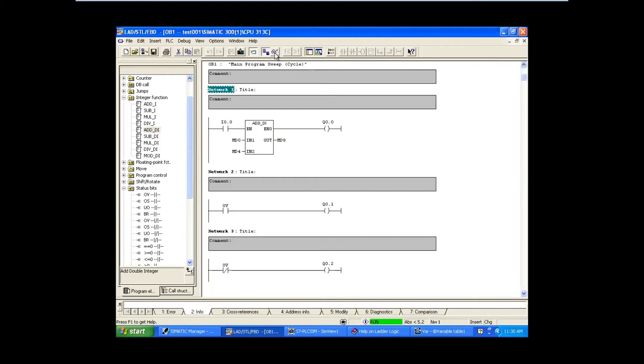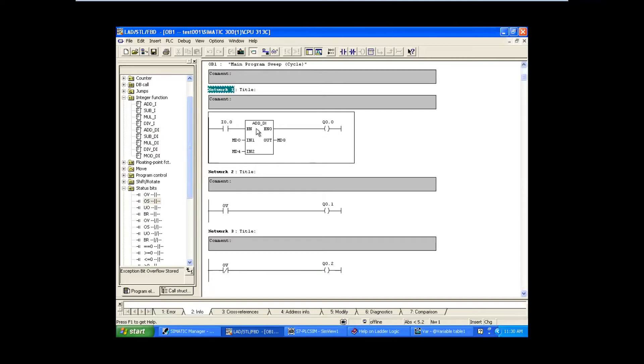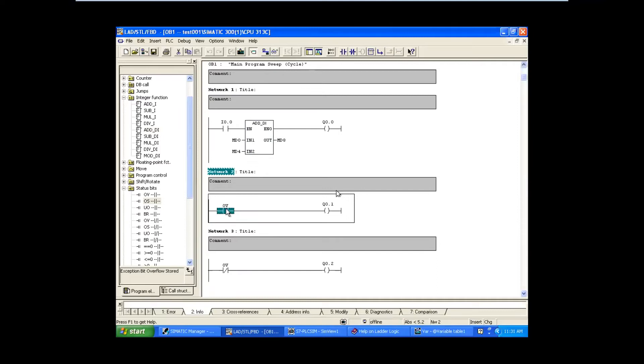So now let's see what is overflow stored. Now there is only one rung with overflow and you are capturing that in the next rung with status Q0.1. Suppose if multiple rungs overflow, how do you get the status bit? You would need to put OV after every rung, which would occupy a lot of space - for four rungs you need to add corresponding OV OV OV OV. Instead of that, we have one option: exception bit overflow stored.